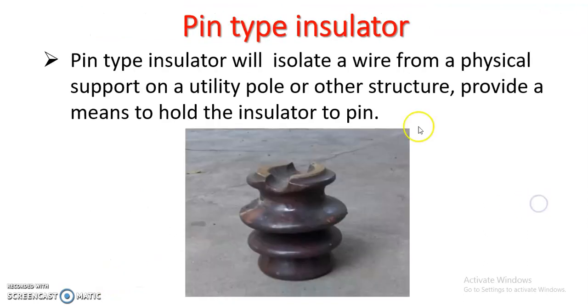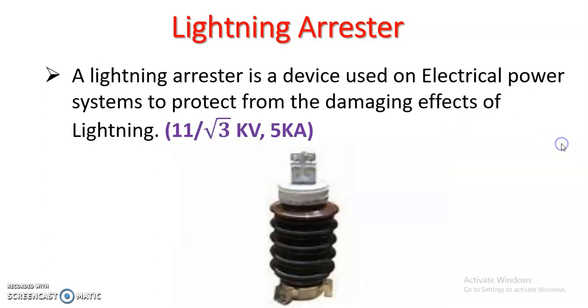Then first is the pin type insulator. That insulator will isolate the physical support from your conductor. That means your pole or supporting structure will be isolated from the conductor. Then lightning arrestor. With the help of the lightning arrestor, you can protect the transformer or plinth mounted substation from lightning stroke or lightning over voltage. The rating of this lightning arrestor used in a plinth mounted substation is 11 by root 3 kV and the current rating is 5 kiloampere.